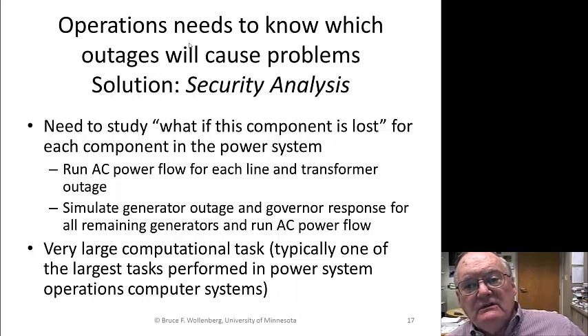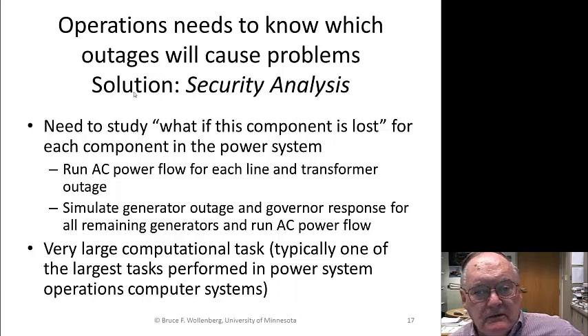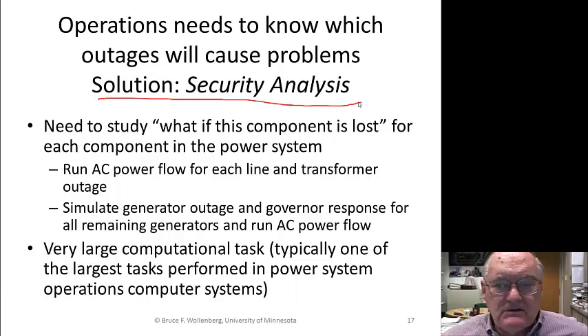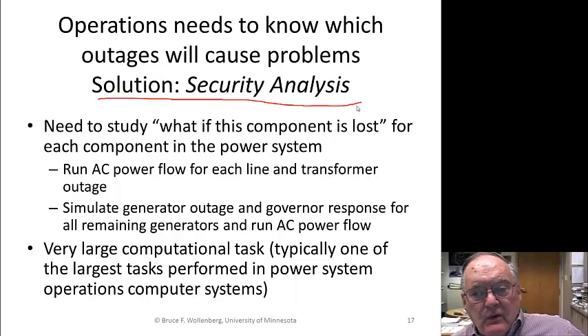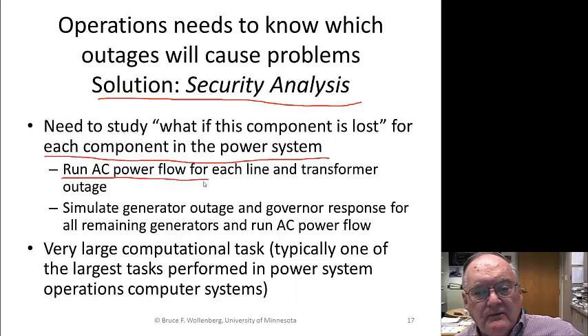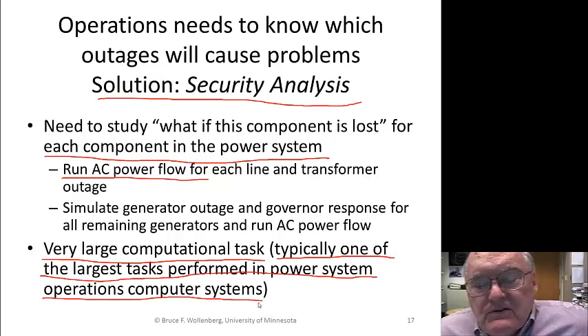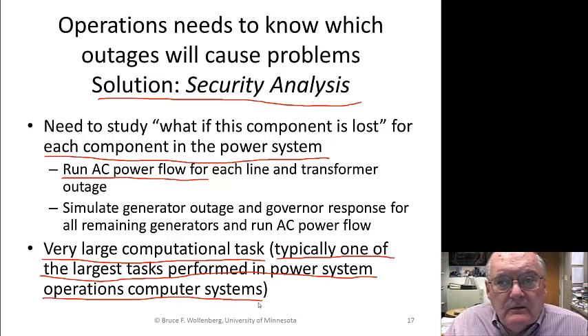Now, operations needs to know which outages will cause problems. The solution we call security analysis, call it contingency analysis, or what if. Need to study what if this component is lost for each component on the system. We'd like to run an AC power flow for each transmission line or transformer outage and simulate generator outage and governor response for all remaining generators and run an AC power flow. The point here is that this is a very large computational task. From my experience working on large control centers, this is one of the largest computational tasks taken up by the computers that run the power system.